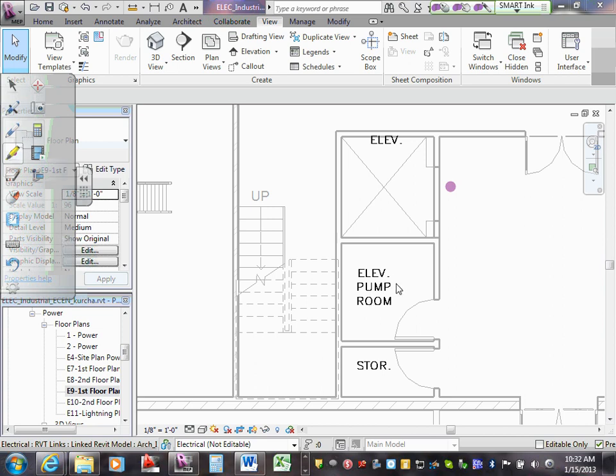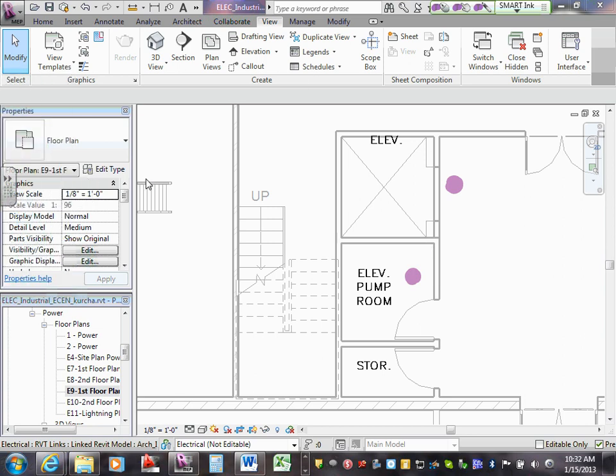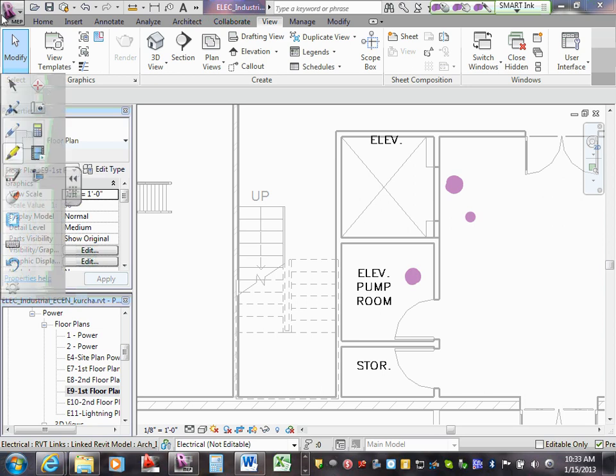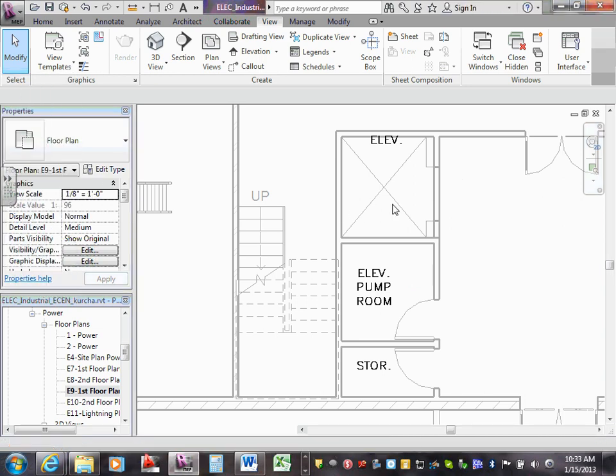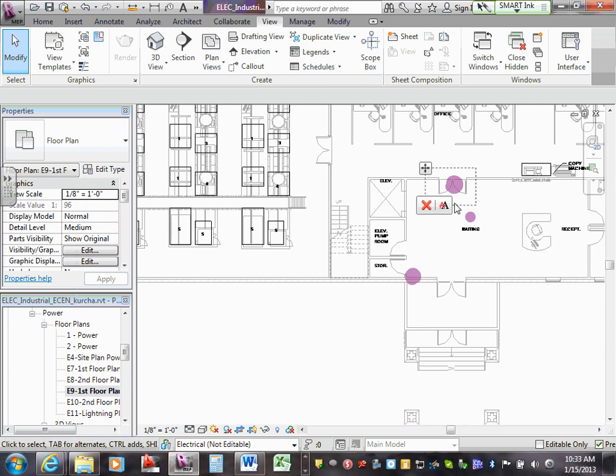One in the room. You're going to have 1 smoke detector in here. Yep. So one here, one here. Yep, and then 1 up on the second floor. One in the second, same spot as this one. And that's going to control your firefighter hat, your primary and your secondary recall. With that, based on if this was just an occupancy fully sprinkled, that would be your fire alarm system.